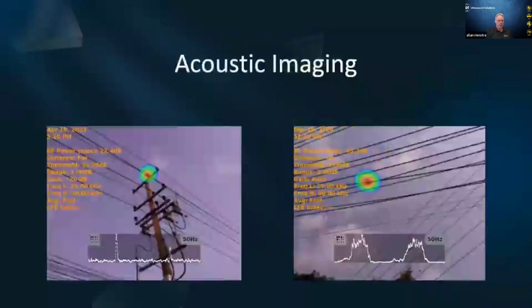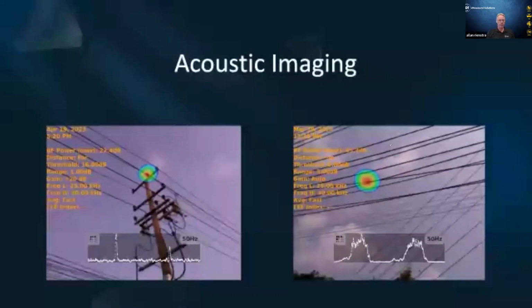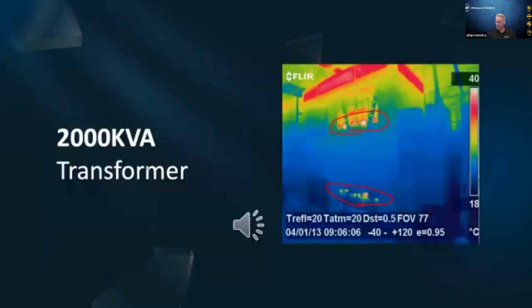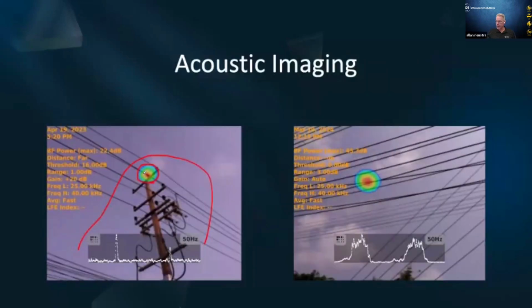So acoustic imaging, this is one of the new toys, or new instruments, that have come out in the market. Really what's happening here is we're taking an array of ultrasound sensors, hundreds in some cases, and putting them in a cluster onto an instrument and then calibrating that to a camera, much like the camera you'd have on your smartphone. And so now we can take an image. If we look at this image of this pole here, we can see from this burst that our acoustic imaging camera is picking up a burst of energy from that insulator.